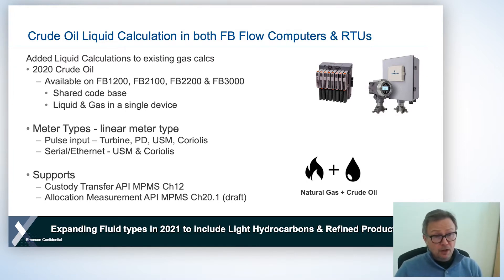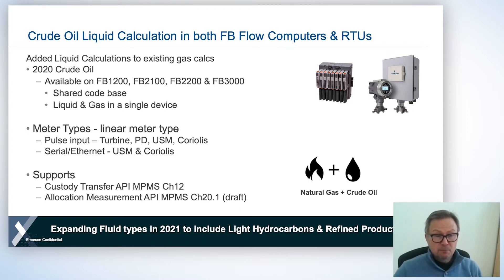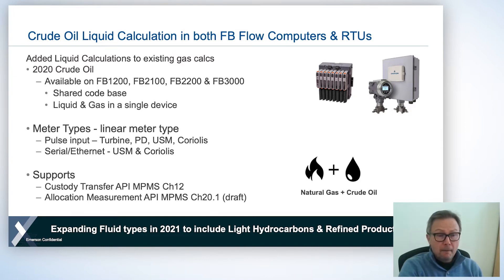We support both custody transfer measurement and allocation measurement. Most of you will be familiar with custody transfer measurement, which is to API Chapter 12. The allocation measurement is to API Chapter 20.1, which is a draft standard at the moment. It's undergoing some major updates with the committee, and we expect it to be published in the next year or so. We've taken it on board to support some of the allocation measurement methods in our standard firmware.